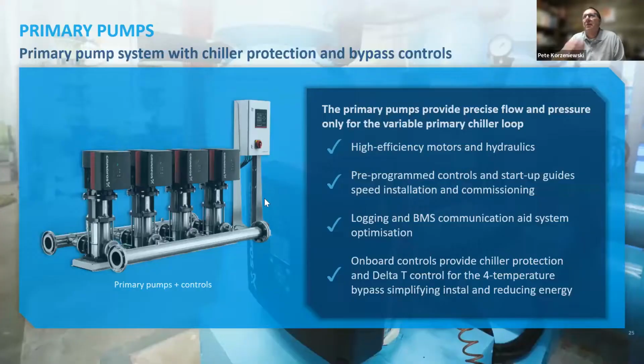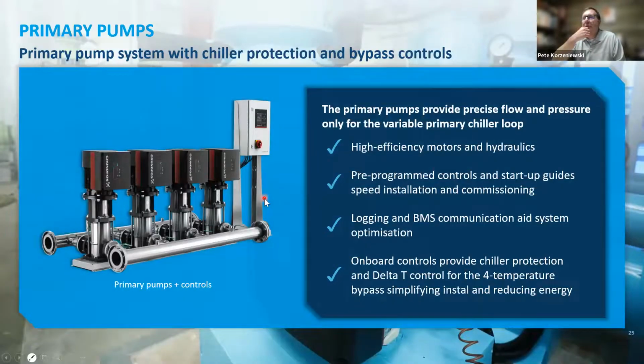So if we look at the primary pumps, it's basically a typical primary pump set with controls, and the controls are going to have two functions. First off, our priority is going to be around chiller protection, and then secondly, we're going to want to manage that bypass, which I'll talk about in a little bit. And when we're looking at prefabricated pump skids, everything is sized for the load itself. The head is minimized in the distributed pumping system. And with these onboard controls, hopefully they're pre-programmed, and you've got the opportunity for BMS and different logging optimization.